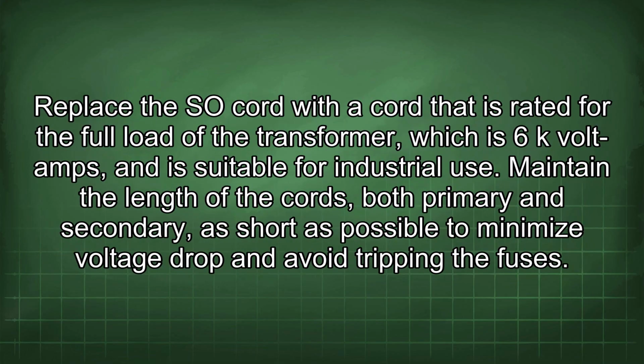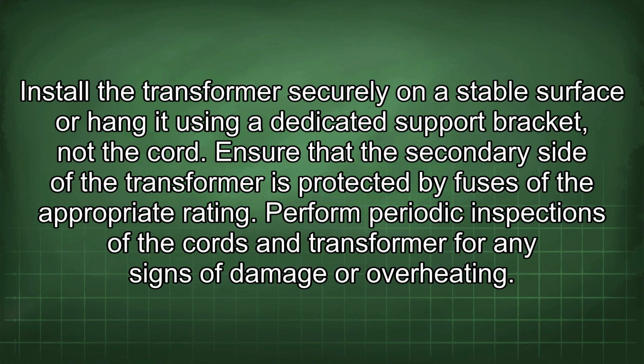Replace the SO cord with a cord that is rated for the full load of the transformer, which is 6 kVA and is suitable for industrial use. Maintain the length of the cords, both primary and secondary, as short as possible to minimize voltage drop and avoid tripping the fuses. Install the transformer securely on a stable surface or hang it using a dedicated support bracket, not the cord. Ensure that the secondary side of the transformer is protected by fuses of the appropriate rating.